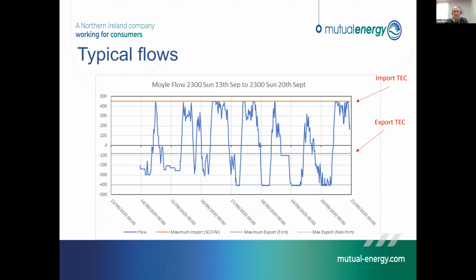I've highlighted a couple of constraints there. We have an import constraint of 450 on import into NI, and an export constraint of, at the time, 80 megawatts into Scotland. National Grid would release additional capacity beyond that on a day-ahead basis, depending on wind conditions. That 80 megawatts has now been lifted to 270, and by the end of the project next year, we expect to have 500 megawatts unconstrained flow into Scotland. We're working with SONI at the moment to lift the 450 constraint into Northern Ireland, so we're hopeful that by 2024, we'll have 500 megawatts carefree in both directions.